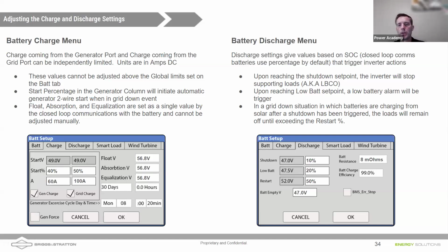It depends a little bit on how frequently you plan to discharge. So if you've got a system that's charging and discharging every day, Daniel and I would generally recommend a shutdown percentage of 20% to get the most number of cycles out of your battery. But for a battery backup system where it's just sitting there topped off waiting for an outage, you might allow this to come all the way down to 0%. So our batteries are warranted all the way down to 0% discharges. Just to extend the lifetime of your batteries, for frequent cycling, we would recommend a 20% reserve.